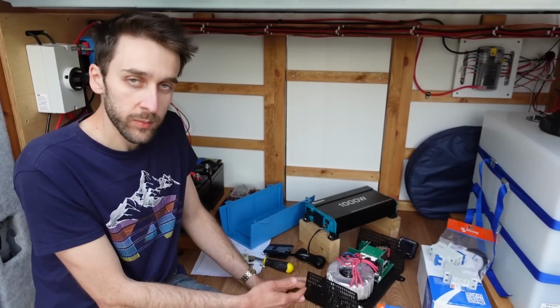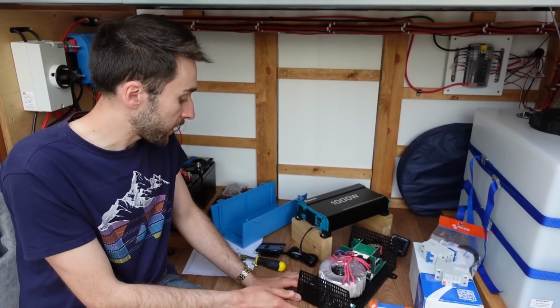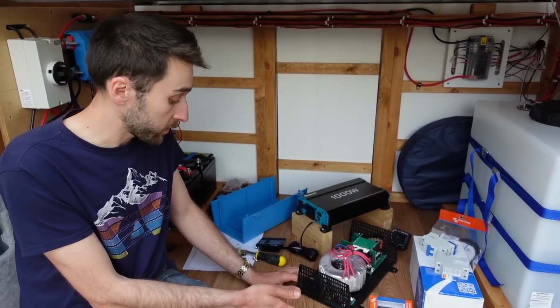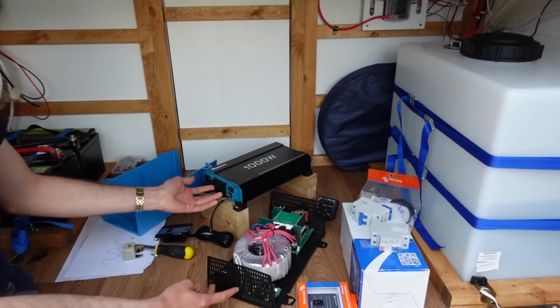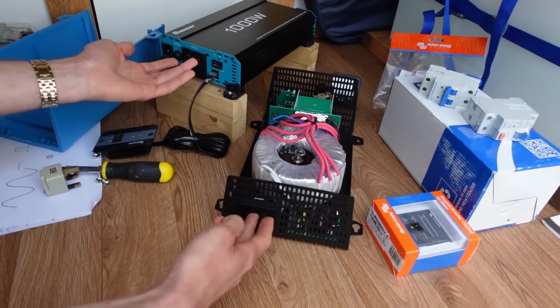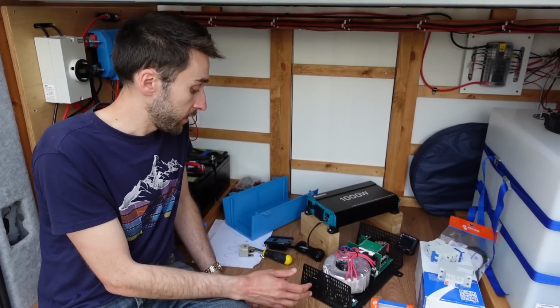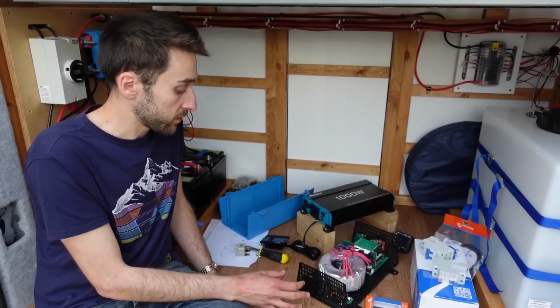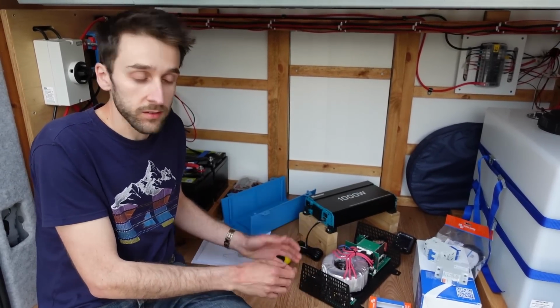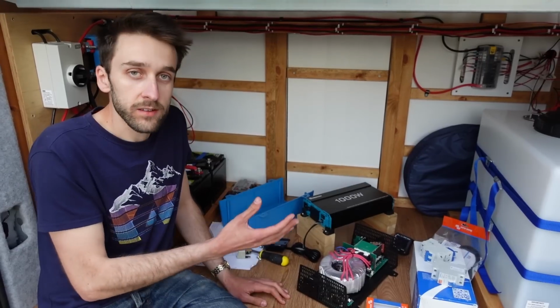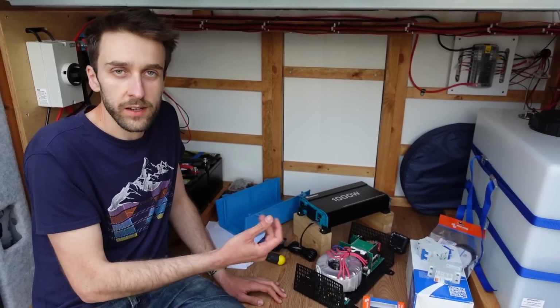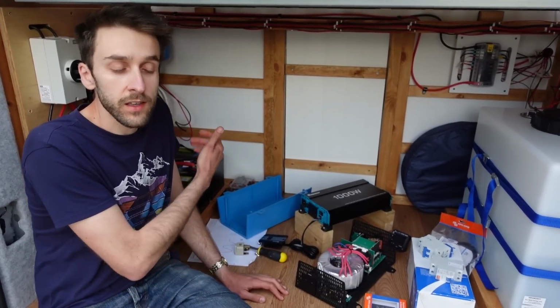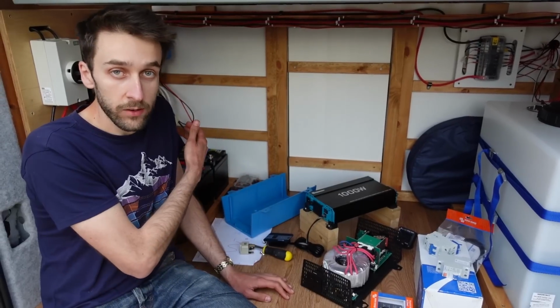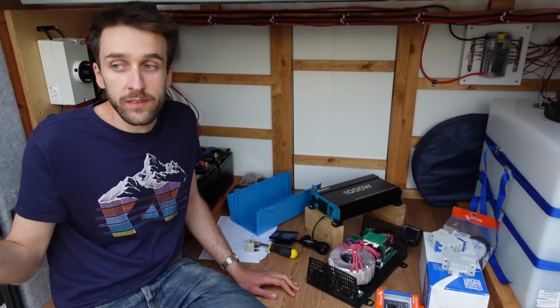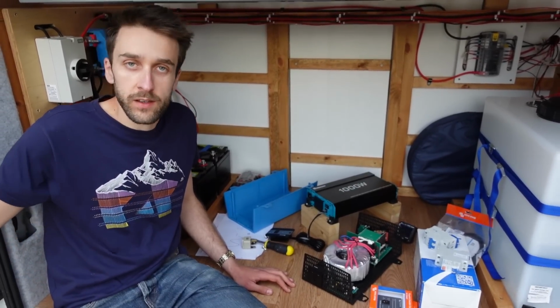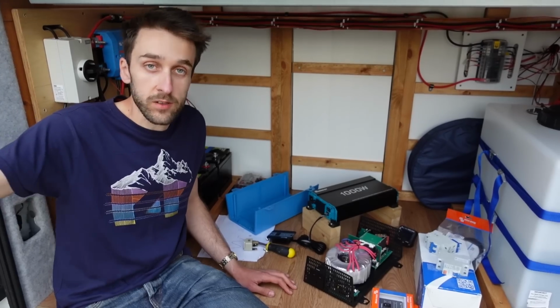From what we understand, these types of inverters are only designed to power a single device at a time, which is why they only have one physical socket. They're set up as floating systems, meaning there's no reference or connection to earth. In the van we've got no normal earth connection anyway, but we've got the van chassis, or if we had shore power - hooked up to the grid - we could also be plugged into the earth connection in the electric supply.